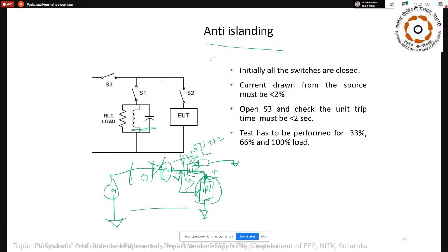How do we normally do the testing for this? This is the inverter unit which I am talking about. This is my grid. S3 is closed and S1 is closed, so the grid is present over here. The unit will start by pushing the power. Whatever the generation power is, it is equal to the load power requirement. Under that condition, I need to check. What we need to incorporate here is a way to identify this particular condition.